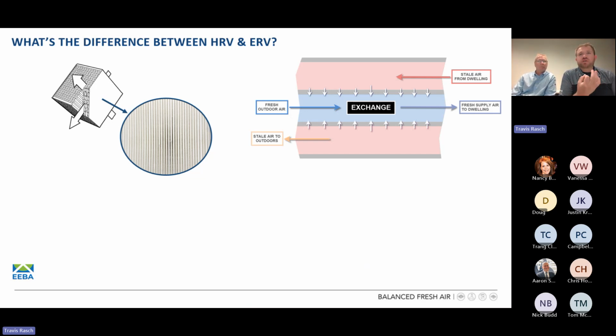Within each of these air channels, if we do a cross section, let's say it's a cold day outside and we've got our house being warmed up. We've got that cold air coming in through one side of the channel. There are alternating membranes essentially. The air paths themselves don't touch, but instead we're using simple thermodynamics to let the cold air in this case be warmed up by the stale air we're moving from the building. So hot goes to cold and wet goes to dry. We're utilizing this fairly simple technology to temper the air that we're bringing in from the outside, while in the same fashion pulling that stale, polluted air from the dwelling at the same rate. Again, you can see how we're utilizing those air channels and ultimately that membrane, which allows that exchange to occur between the fresh outdoor air and the stale indoor air that we're pulling from the dwelling.